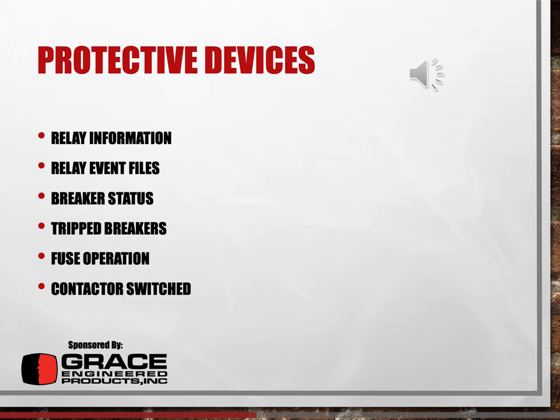So for protective devices, what are you really looking at? I've touched on this a little bit today, but you definitely want the relay information. You want the protection settings. You want to know what type of protection this circuit is protected by. You want to know, were there any disturbances or short circuits in the past year or 2 that could have damaged the equipment, that could have caused this failure that just lingered over time and then eventually failed catastrophically? You want those relay event files. You also want to jot down the status of the breaker before the accident and after the accident. Maybe it changed. Maybe it didn't change. And if it didn't change, why? If it didn't trip, why?